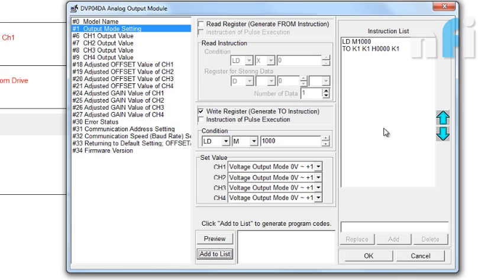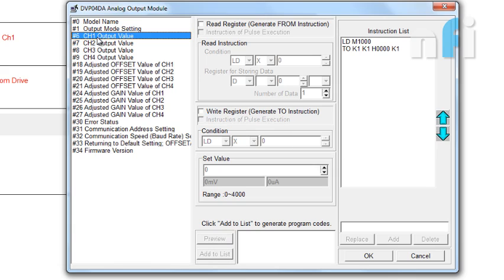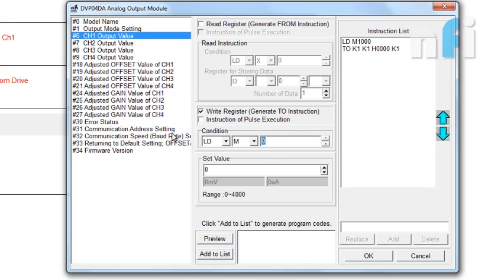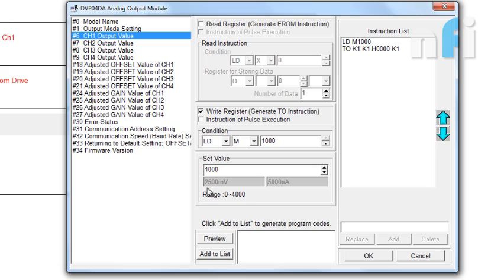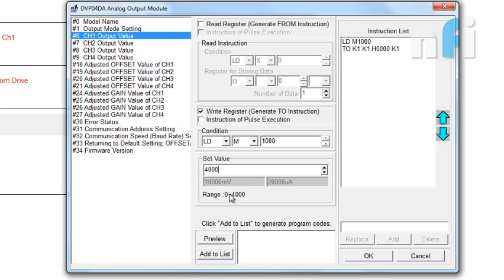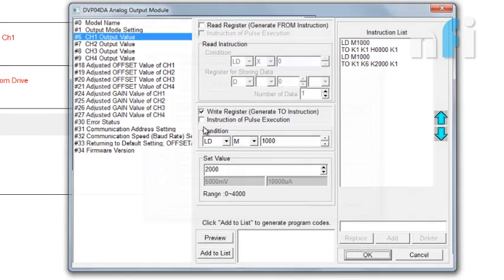Right now I need 0 to 10V, so that mode is set. Going to instruction list. Channel 1 output voltage - here I have to write the value. The condition is I want values to be written every time. So set value - you can see here conversion automatically, range is 0 to 4000. If I enter 0 it will give you 0V. If I enter 1000, 2.5V. If I write 4000, 10V. Let's initially write 2000. Add to list. Okay.